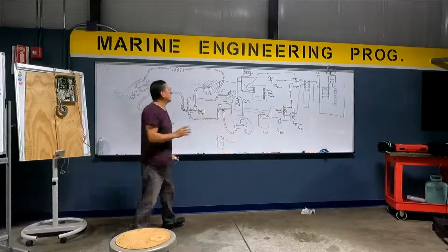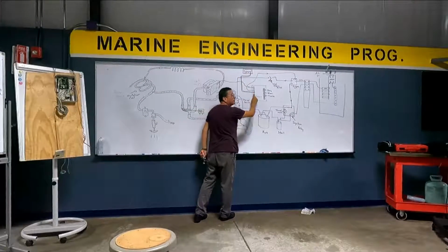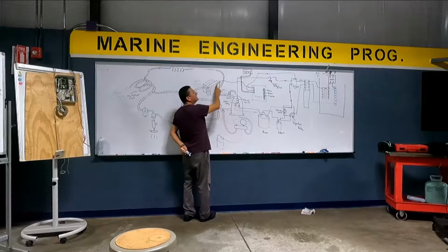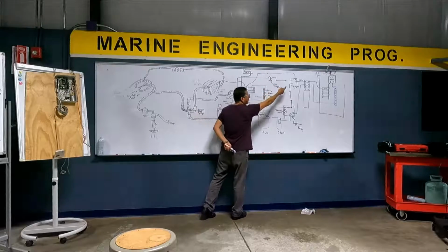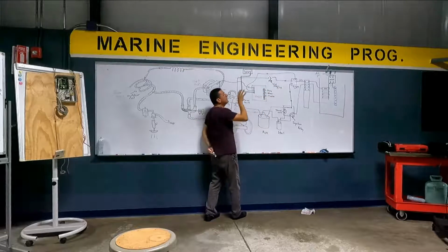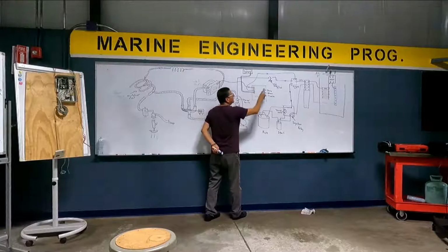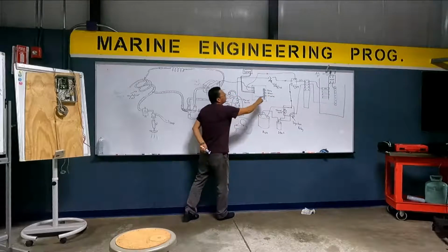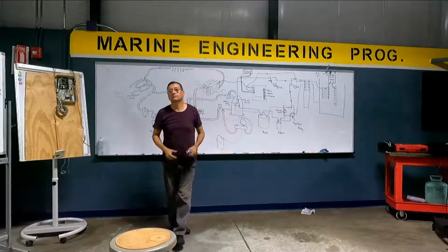Everybody understand? The secret is what temperature entered here from the thermostat. The thermostat does the comparison with this sensor and sends the signal to activate the triac, and also internally sends the signal to activate the pump, the blower, or the Y valve if it's in heating or cooling mode.